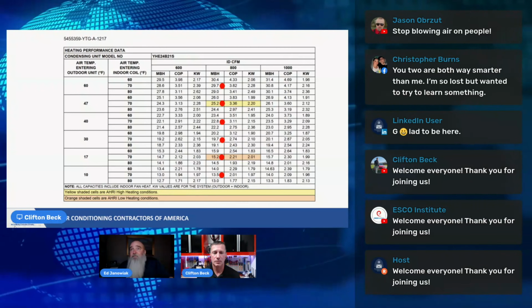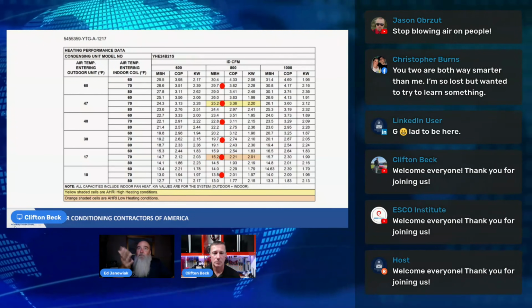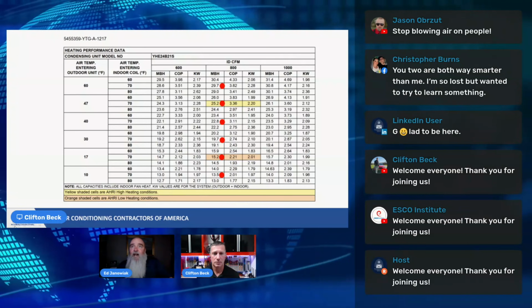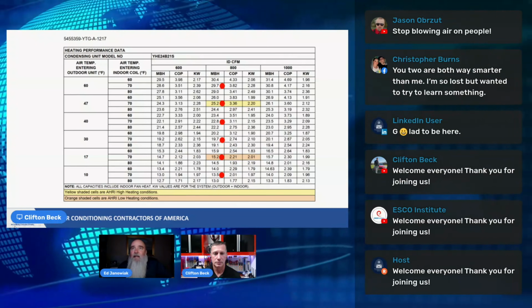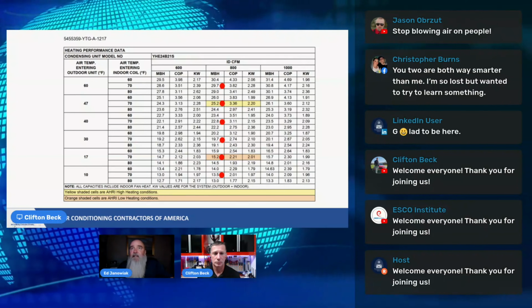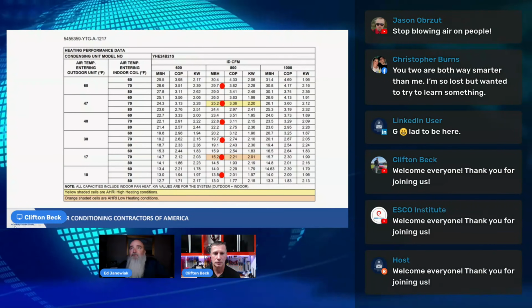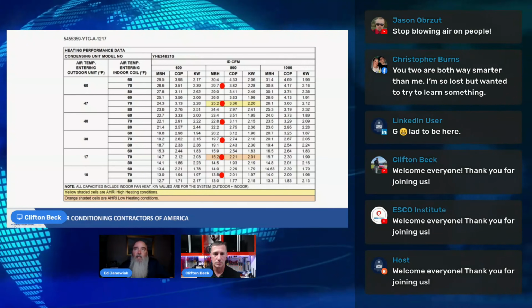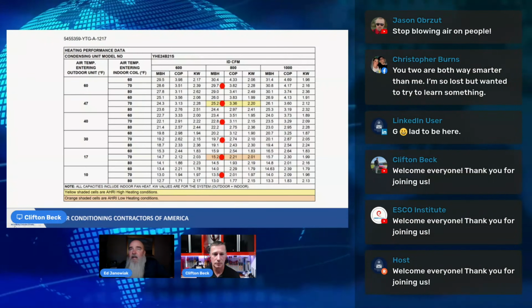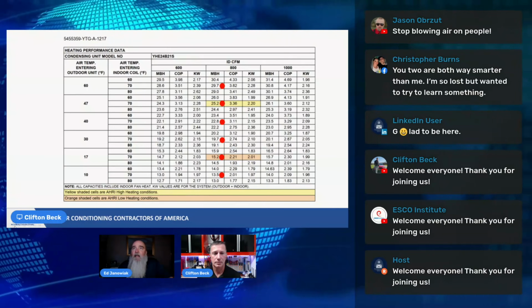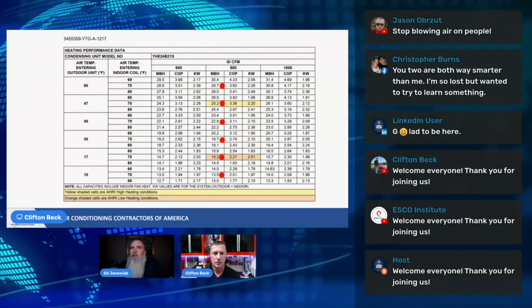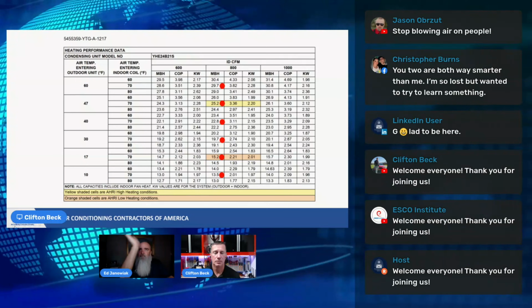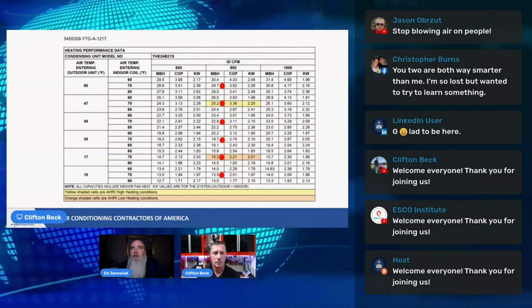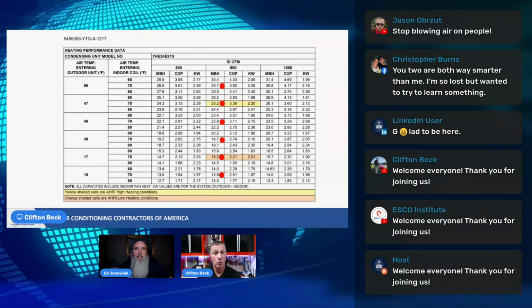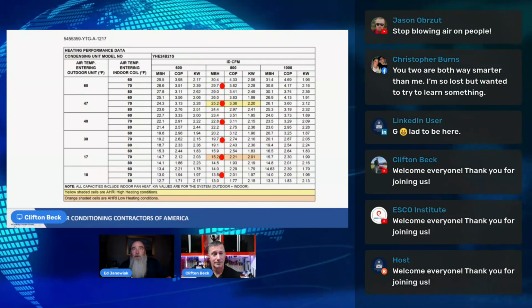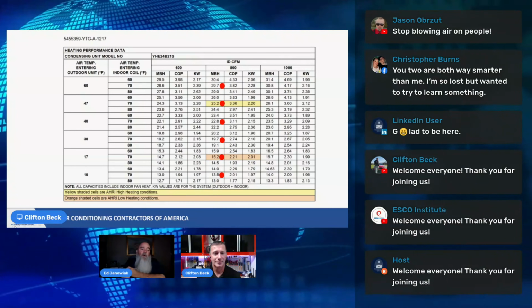if we go and pick any of those dots, let's just take the top dot at 60. And if I go to the left, I see at 70-degree entering air temperature, 28,600 BTUs at 600 CFM for that nominal 2-ton heat pump. That is right. And I got a COP, what's it saying, like 351? 3.51. Right. So if I go to the right under 800 CFM, I see my COP increase, and I see my total BTU output increase. That's right. If I go to the right, I see it go up again.